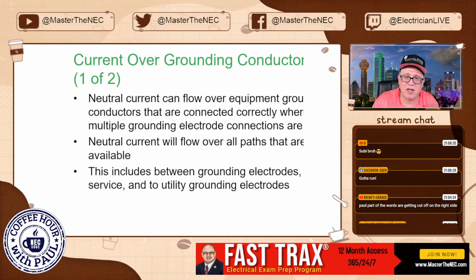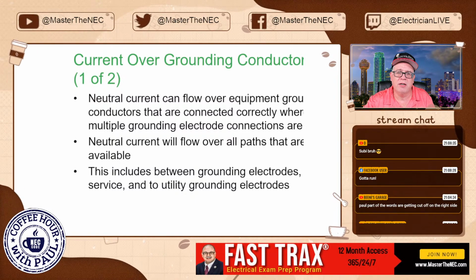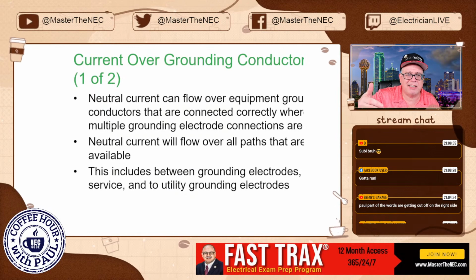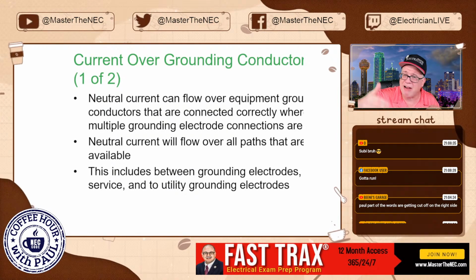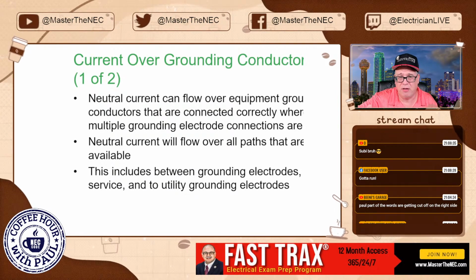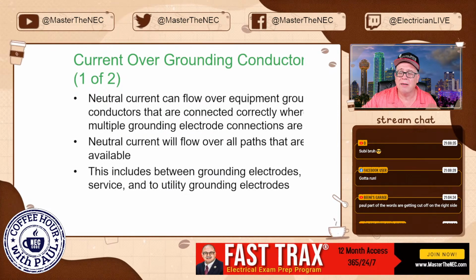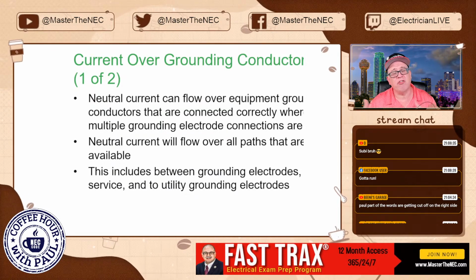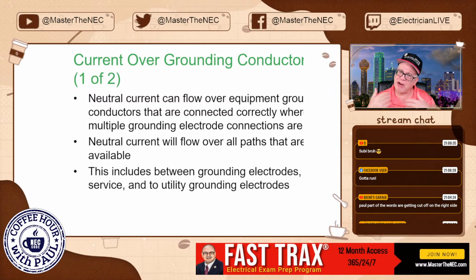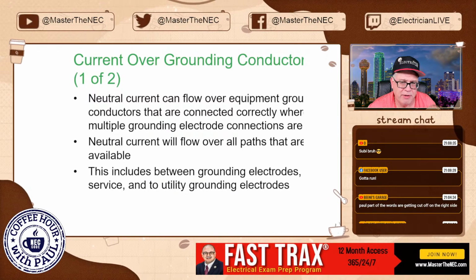Okay, there's allowances in the code for existing applications for you to use the grounded conductor for things like dryers and ranges that have been around for decades. And we can't do it anymore, but they are allowed. And those connections are permitted, but that goes directly against what we're trying to achieve.